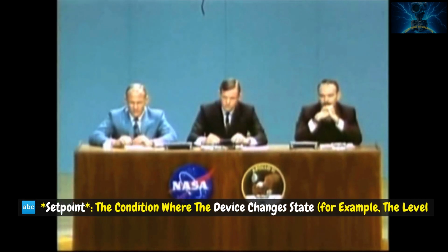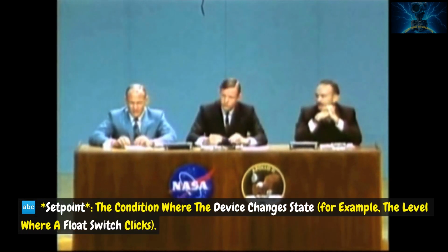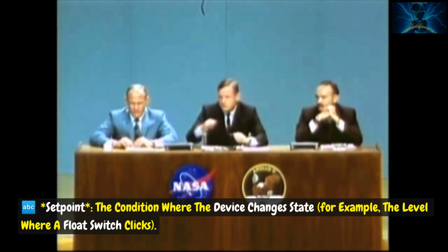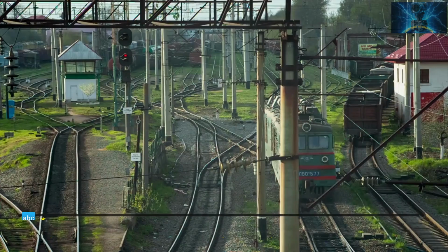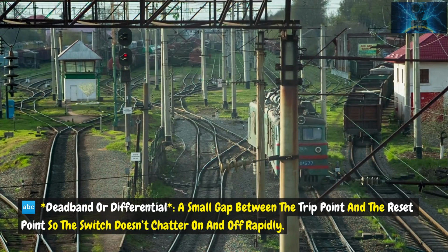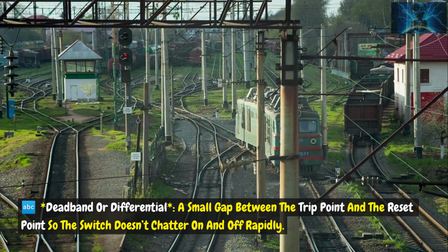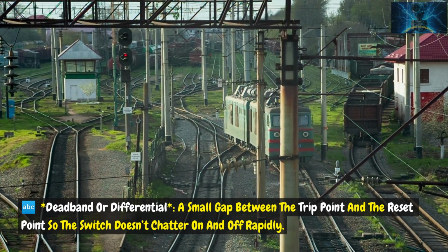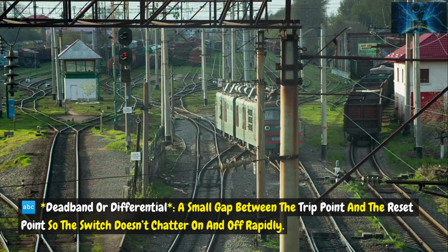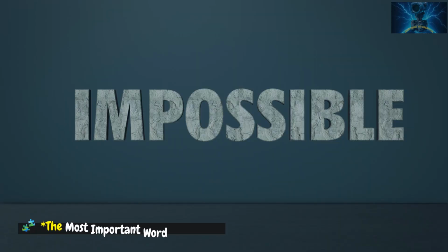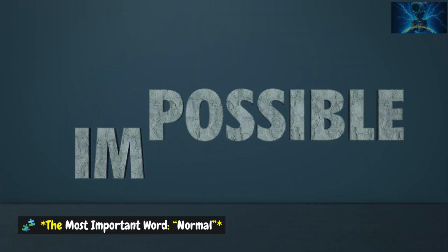Set point: the condition where the device changes state, for example, the level where a float switch clicks. Dead band or differential: a small gap between the trip point and the reset point, so the switch doesn't chatter on and off rapidly. The most important word: normal.